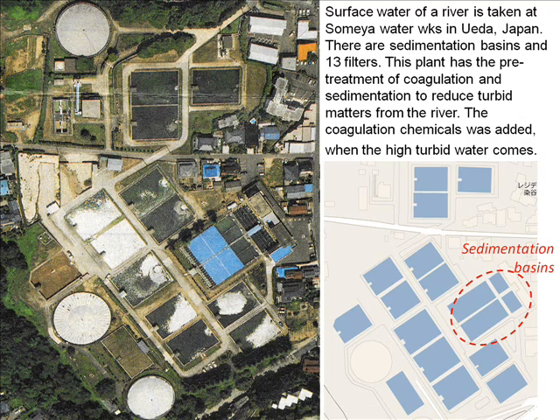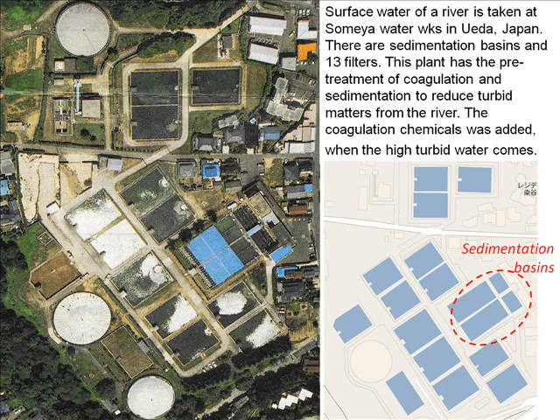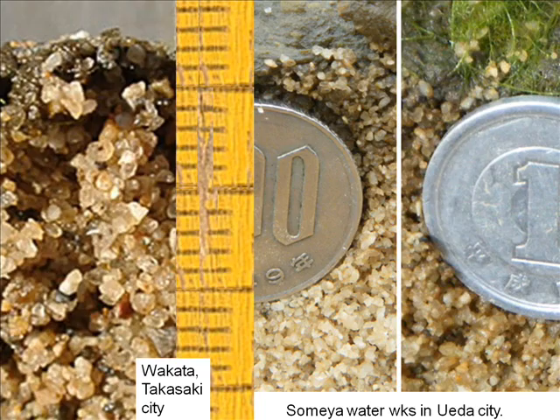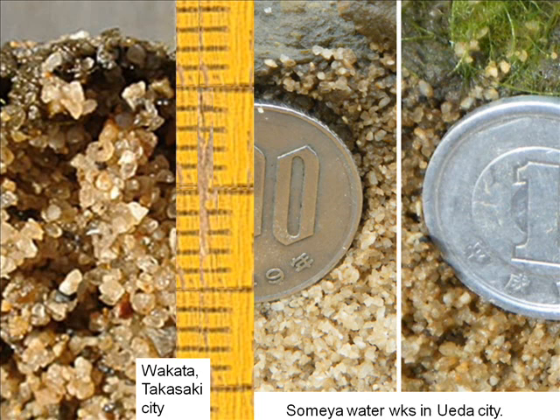Surface water of a river is taken at the Ueda Water Works in Ueda, Japan. There are sedimentation basins and 13 filters. This plant has pretreatment of coagulation and sedimentation to reduce turbid matter from the river. Coagulation chemicals are added when high turbidity water comes. In Ueda City, small size sand is used — this is the normal standard size. I checked the profile of the sand column near the surface. Dirty matter does not enter the deeper layer in both plants. Wakata sand is larger than Ueda sand. In Ueda City, the sand may be darkened a little. They sometimes use coagulant. I feel there is a slight effect of chemicals on the biological community in Ueda City.